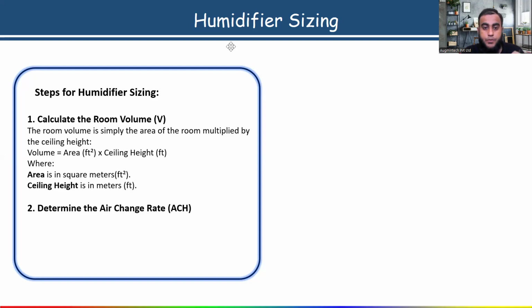Below the ceiling I'm talking about. I don't know your name. See, the ceiling height, why do we need to take the ceiling height if you're calculating the room volume? Because below the ceiling only we have to supply the conditioned air, right? Above the ceiling we are not supplying conditioned air, okay? So that is why you have to consider the ceiling height. Don't need to consider the height up to the slab level, okay?